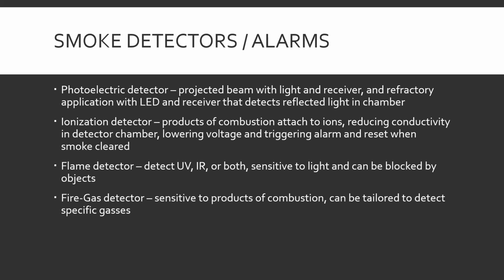The refractory application with LED and receiver that detects reflected light in a chamber. How that one works, it's the same kind of premise but done a different way. Instead of having a light over there and a receiver over there, it's one unit with an LED that shines in a specific point. And as long as that light is shining at that specific point, the detector doesn't see it and it goes, no light, I can't see the little LED. It's cool. When smoke gets into the detector, the light hits the little smoke particles and reflects and bounces around. And it can hit the actual receiver and the detector, which then makes the detector go, wait a minute, I'm detecting the LED light. I have to sound an alarm.